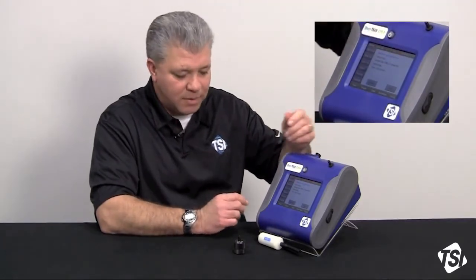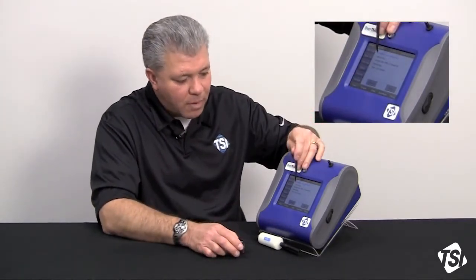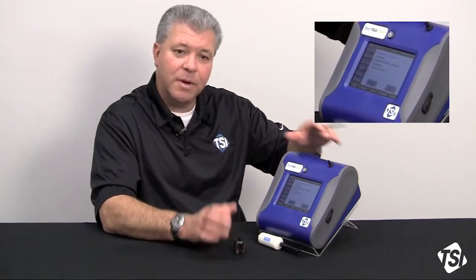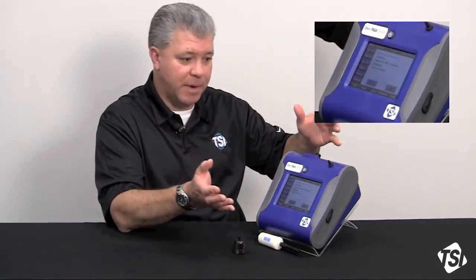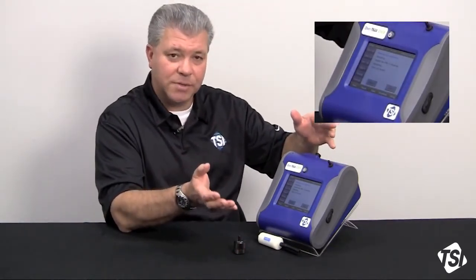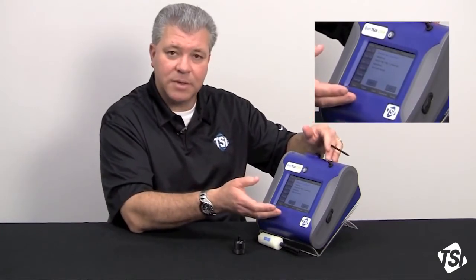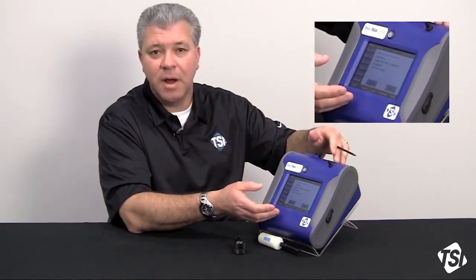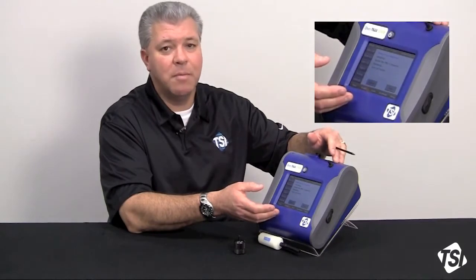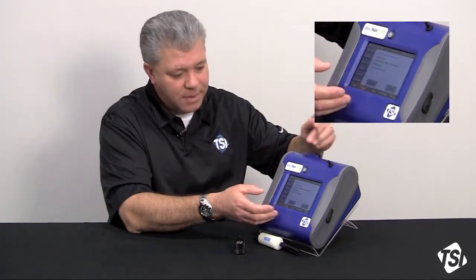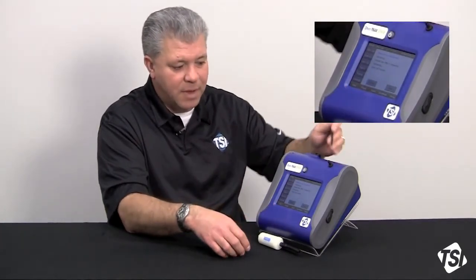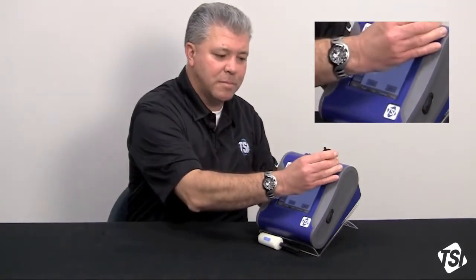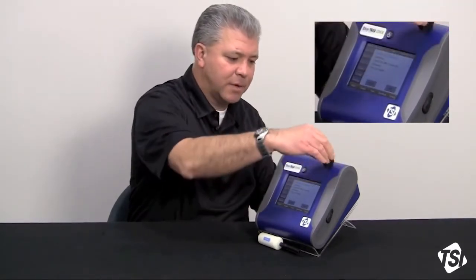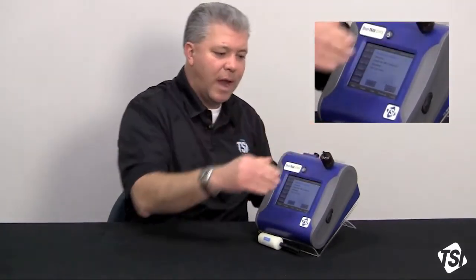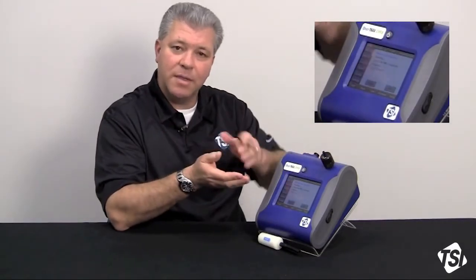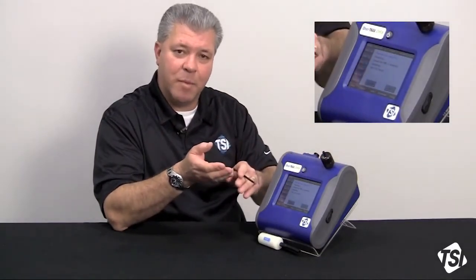So when you sample without the impactor, you're looking at the total dust coming in, or the full detection range of what the DustTrak DRX can see, which is 15 microns down to 0.1 microns or 100 nanometers. So you're going to sample without. Then you're going to sample with the PM 2.5 impactor put on the instrument. And what that's going to do is cut the aerosol size at 2.5 microns.